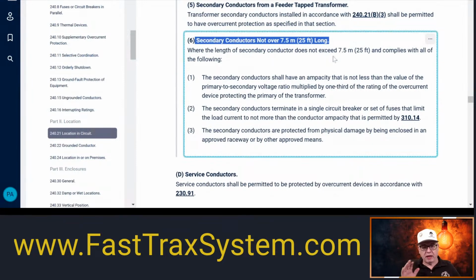And to be honest with you, if you hit the transformer and you're coming up to the secondary, usually the secondary conductors are going to terminate in some type of equipment right there next to the transformer. And then after that, you have your circuits that can go out wherever you want them to go. That's not an issue. We're only limiting the distance on these secondary conductors. All right, so that's what we're talking about here.